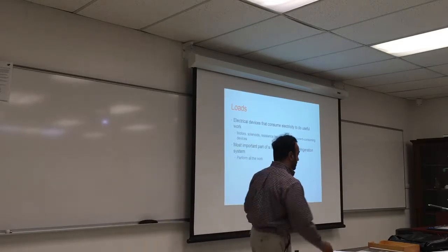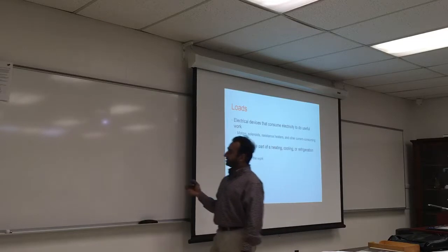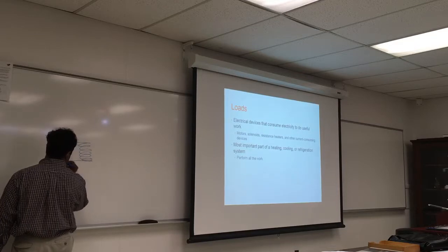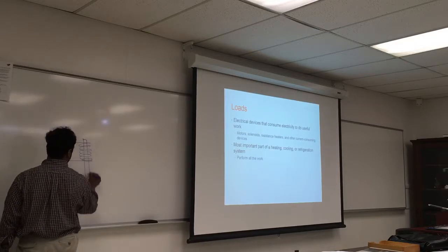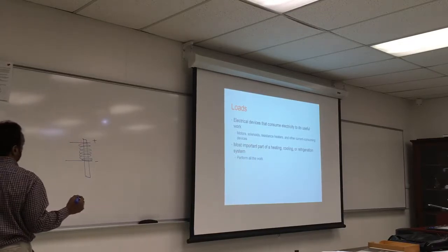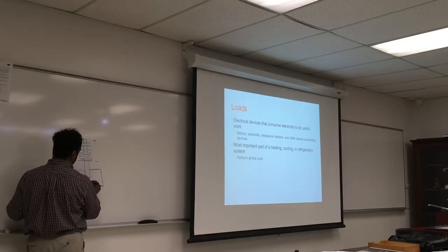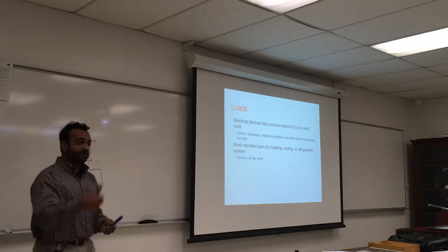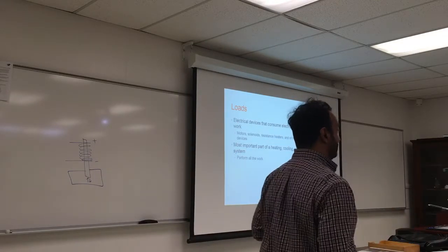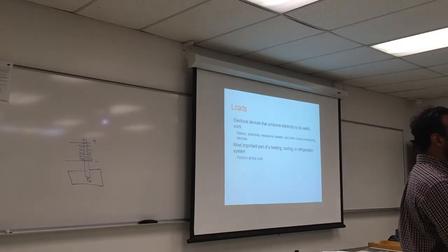Solenoids are valves. We'll talk about solenoids plenty, but a solenoid is a valve that uses electromotive force to close or open a valve. So a solenoid has a stem in the middle, and it follows the magnetic rule for a coil, and this thing goes inside the pipe and goes up and down, either by energizing or de-energizing. So solenoid is referred to any coil that opens and closes a valve. It could do something else. You can use a solenoid as a sensor.